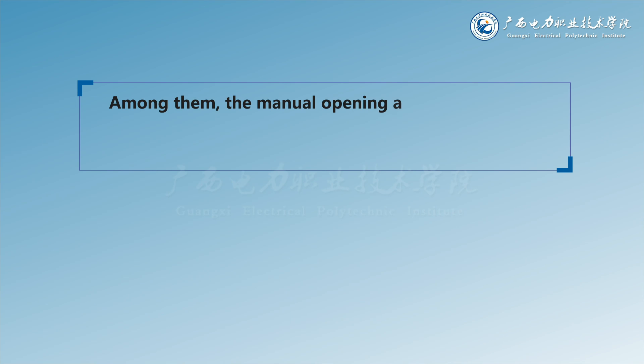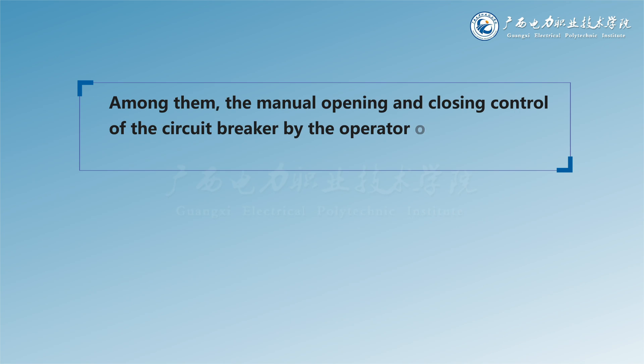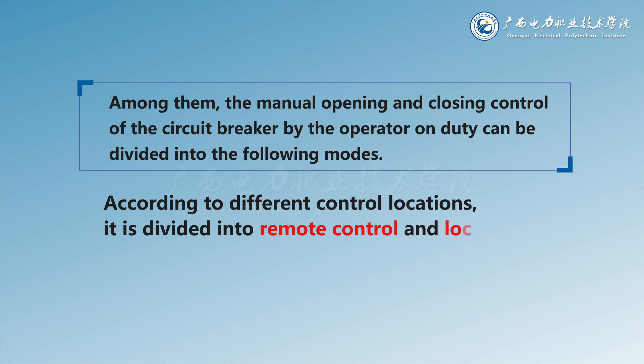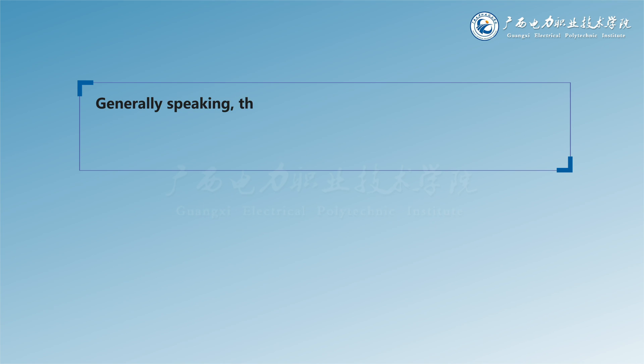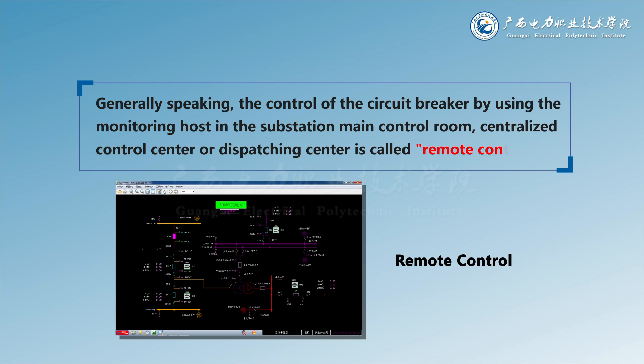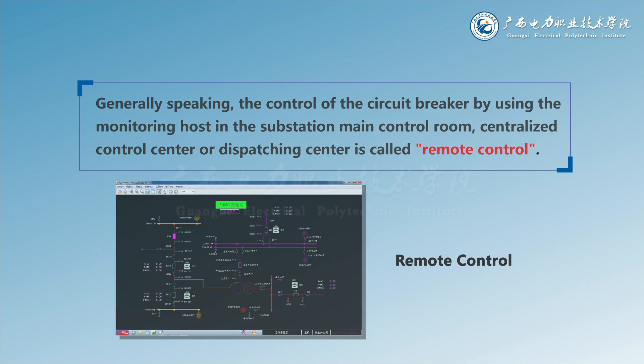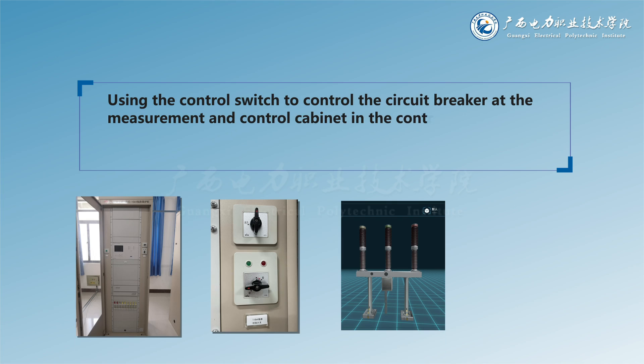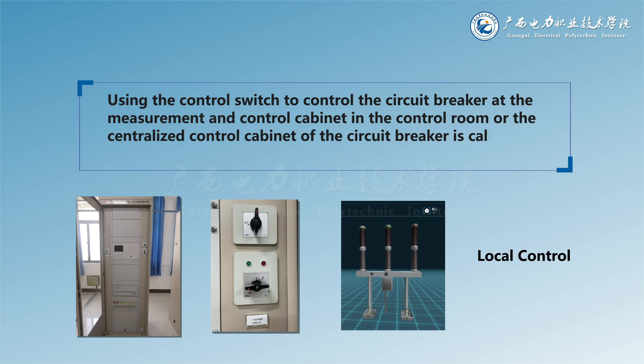The manual opening and closing control of the circuit breaker by the operator on duty can be divided into the following modes. According to different control locations, it is divided into remote control and local control. Generally speaking, the control of the circuit breaker by using the monitoring host in the substation main control room, centralized control center or dispatching center is called remote control. Using the control switch at the measurement and control cabinet in the control room or the centralized control cabinet of the circuit breaker is called local control.